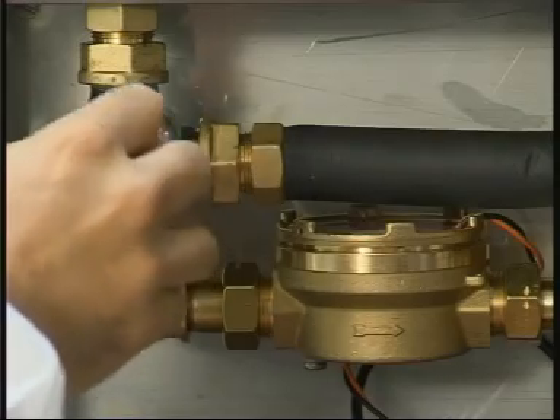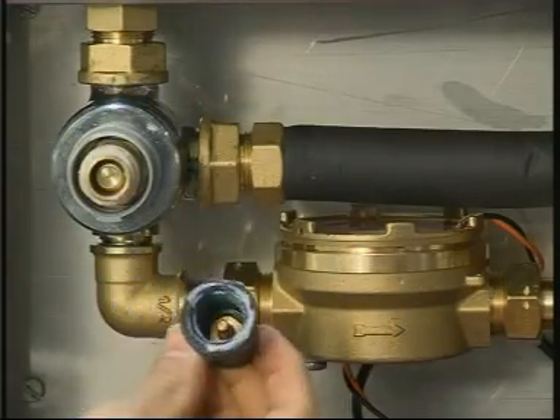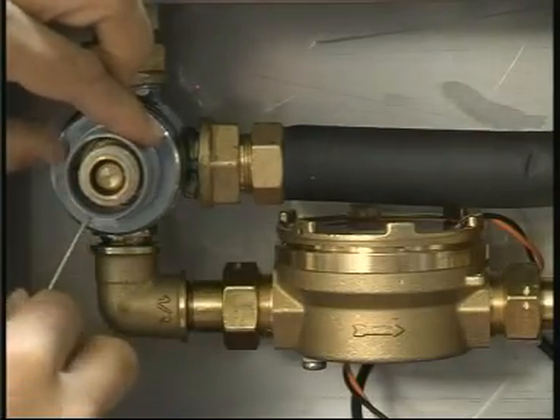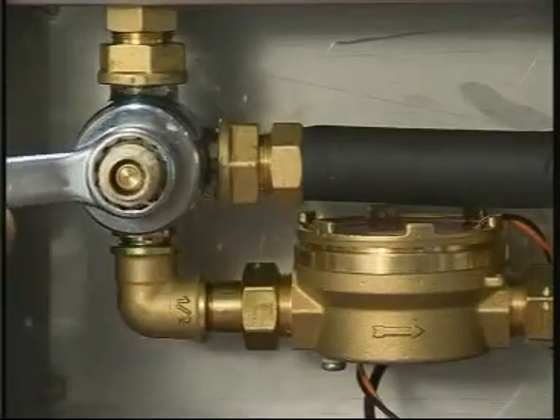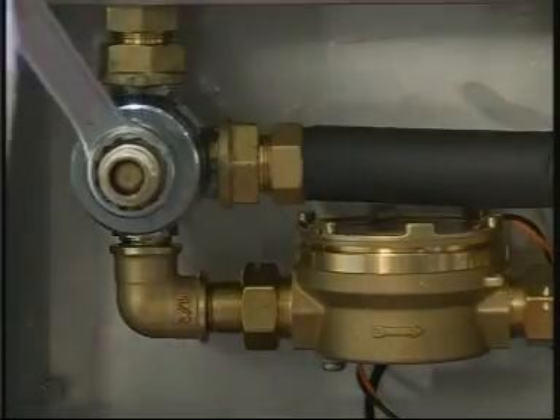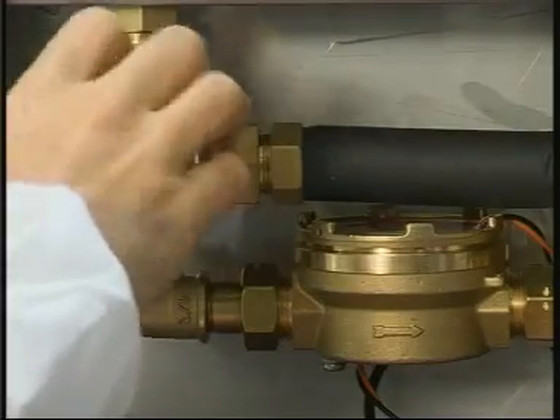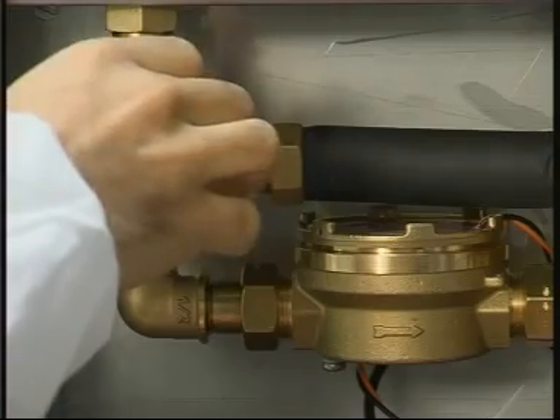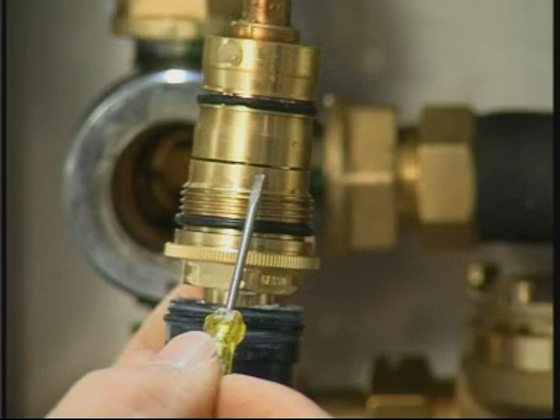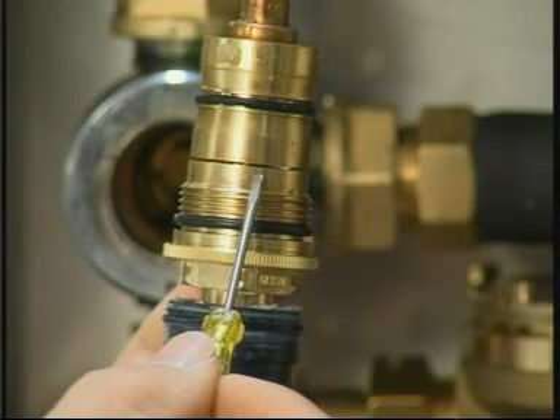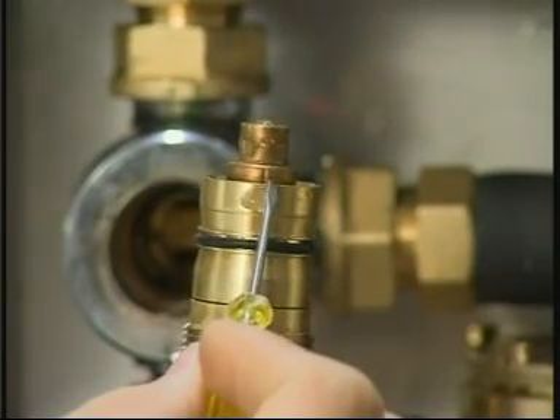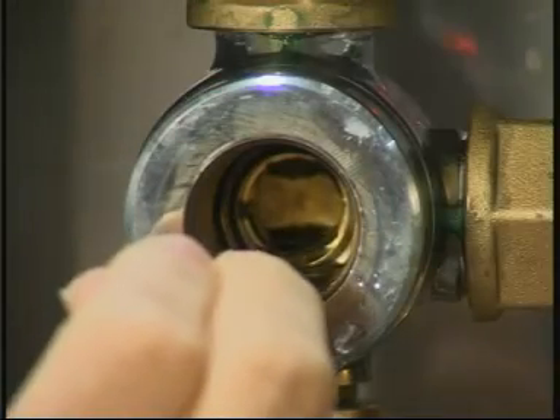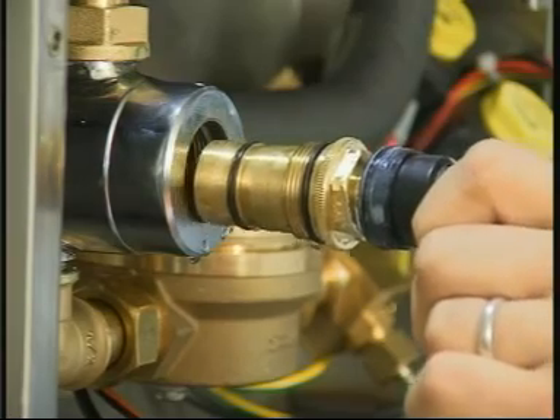Open the machine, unscrew the black pin of the knob, take off the grey plastic fastening ring with a small screwdriver, and after that, with a spanner number 25, turn the thermostatic element anti-clockwise and unscrew it from its valve seat. Using the black knob pin, it is possible to open and close the sensitive element to check that in the closing areas no impurities have been deposited. Furthermore, check the internal of the mixer casing where the other end of stroke of the thermostatic element is.